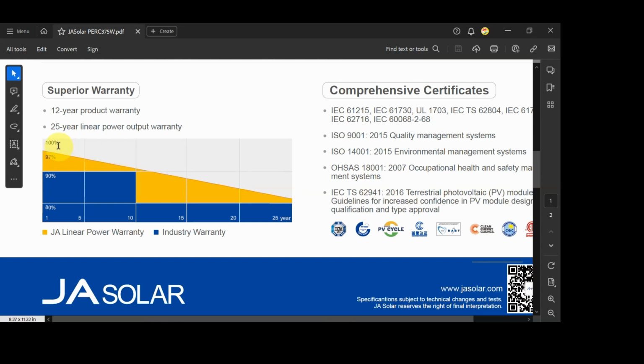So basically, this is what happens when the module is exposed to the sun for the first time. Dia dah akan ada losses dah. And this is the losses due to the specific nature of crystalline modules. When it's exposed to the sun for the first time, there are some chemical reactions involved inside there. Okay, adalah technical lah, dia theory sikit lah. That will cause the efficiency to automatically reduce to 97%. Depending on the manufacturer, some 2%, some 3%. So this is the effect of light-induced degradation.